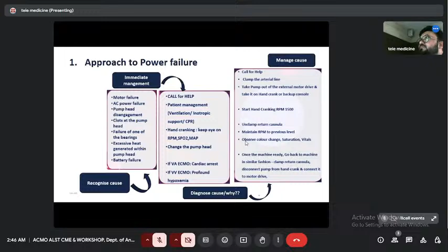And we have to watch the color difference of the tubing and see the SpO2 and mean arterial pressures. Till that time, if there is power failure along with pump failure, change the pump head, or till the power comes, take the hand crank and change that. If the patient is on VA ECMO, there is risk of cardiac arrest because everything is dependent on the ECMO. If VV ECMO, the patient will end up in hypoxia. So again, I told you how to handle power failure. We'll discuss all these things in the stations.